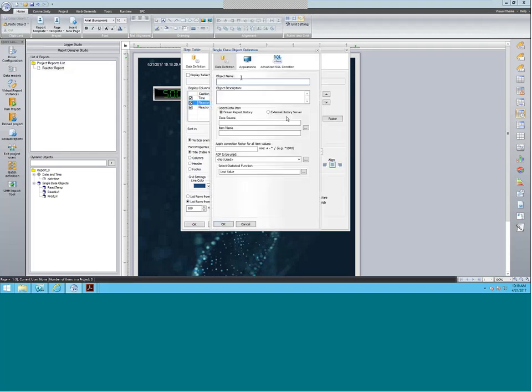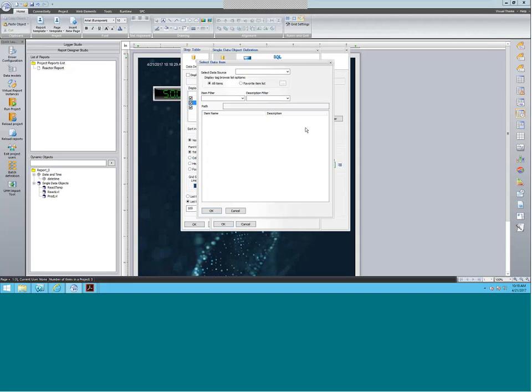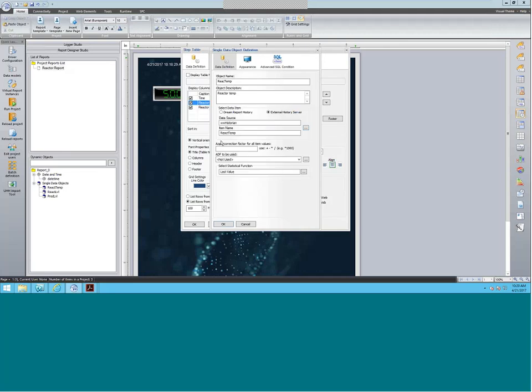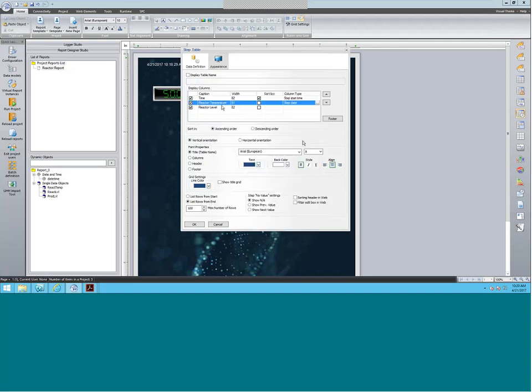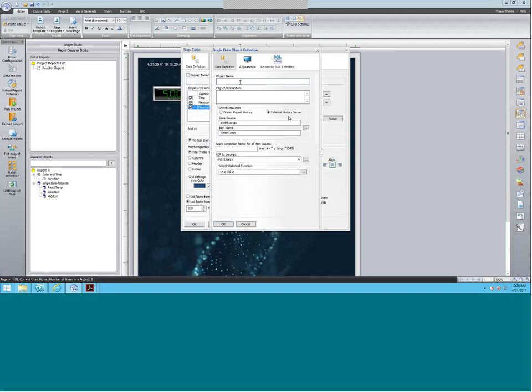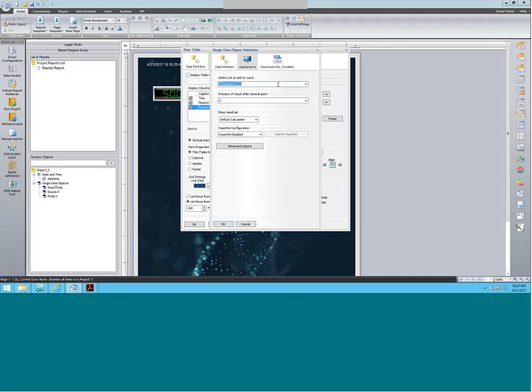Reactor temperature — I'm going to select the step data, give this object a name, then go to analog tags and get the react temp for the temperature. You can also change the appearance, adding units. Then we also have react level here — adding that on there, finding the tags: the react level, and of course the unit.